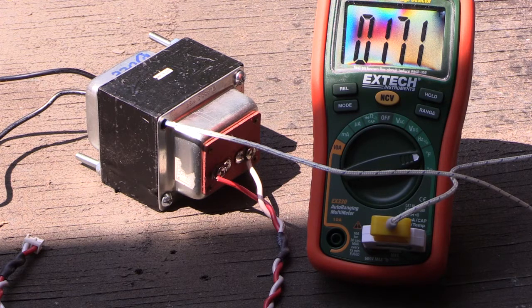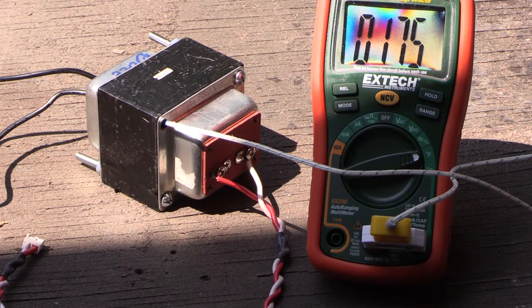What you can envision is these transformers are mounted inside a metal enclosure, inside the wall housing, inside the wall of your house. And if you had 2 failed transformers, and if they're both putting out to a dead short because you've had a dramatic failure in your 4406, you would have 2 fairly solid blocks of metal sitting inside your wall cavity running right now at 175 degrees, which is pretty high. And since it's inside the wall, the temperature is going to go up even higher because there's no cooling inside the wall. So it's going to get very, very, very hot.